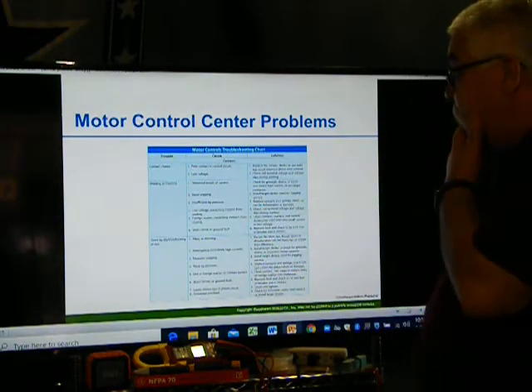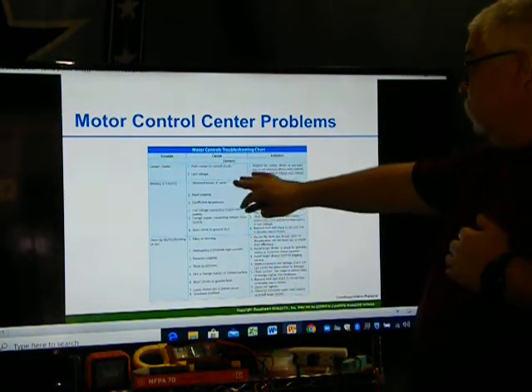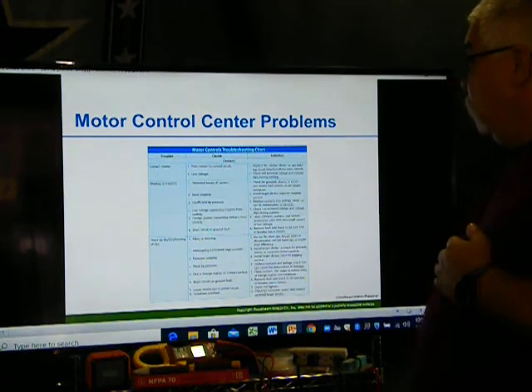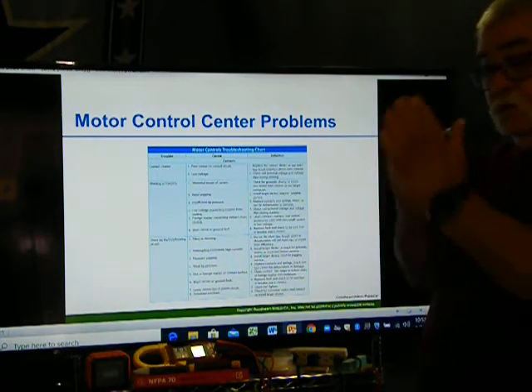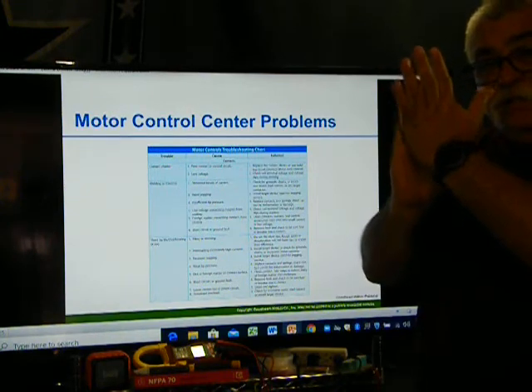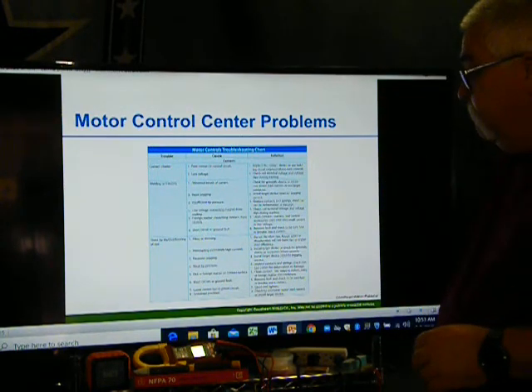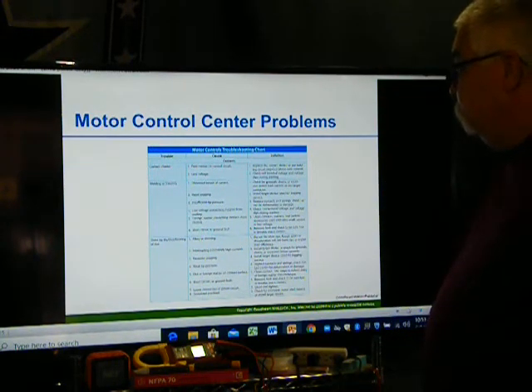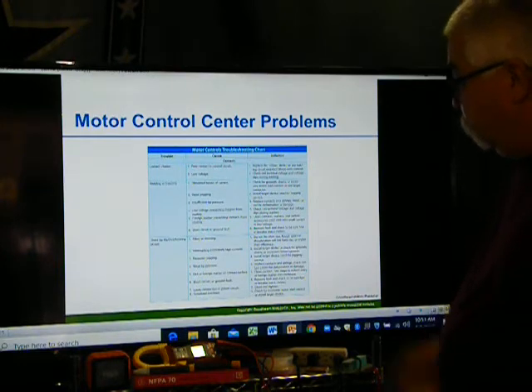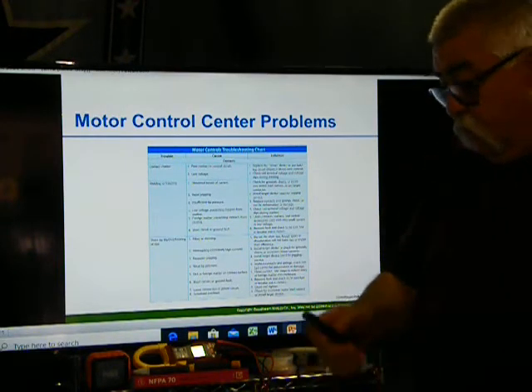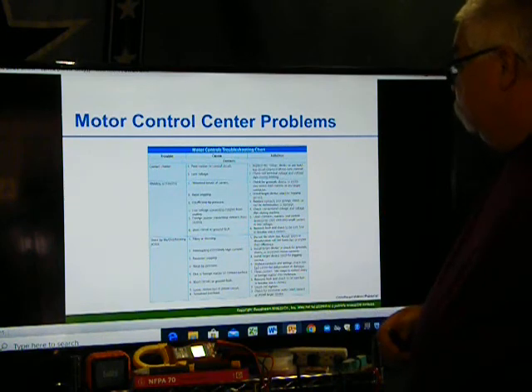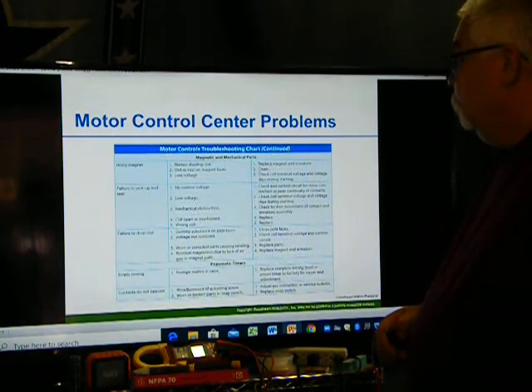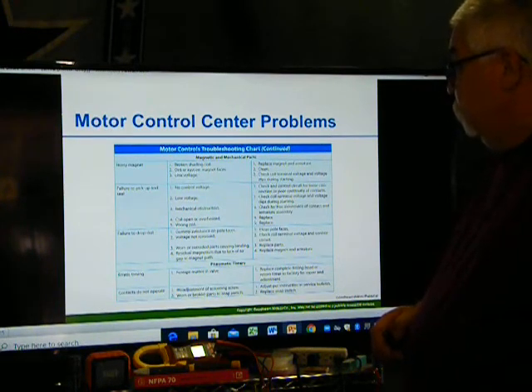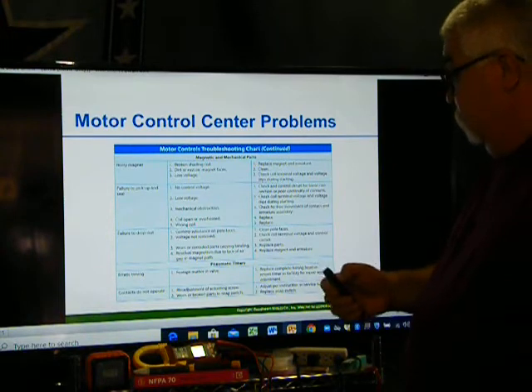So you have here the causes: contact chattering, poor contact control, low voltage. So it sits and it doesn't close, so the motor doesn't turn on. Welding or freezing. Different things that are on there, so read through them. Noisy magnet, broken shading coil, dirt or dust on magnetic faces, low voltage.